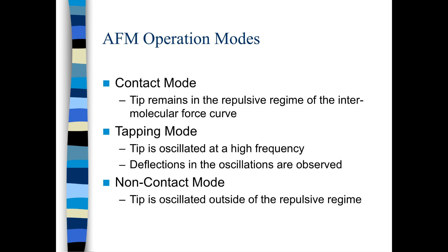There are three modes of operation in the atomic force microscope. The first is contact mode, in which the tip is almost placed on the material and is run throughout the surface of the material, thus imaging it. The tip remains in a repulsive regime of the intermolecular force curve.